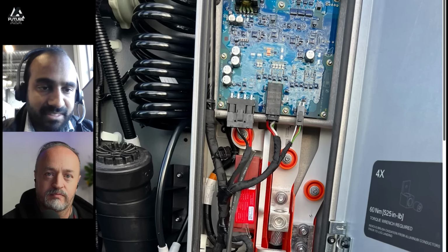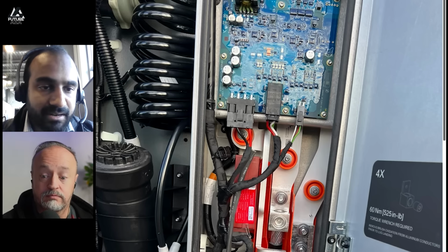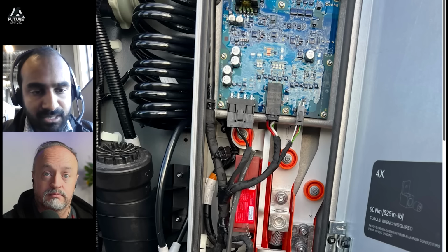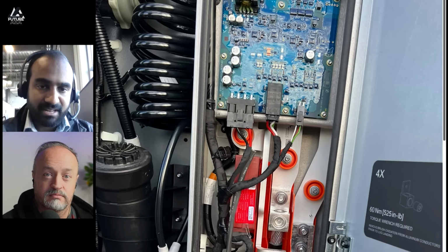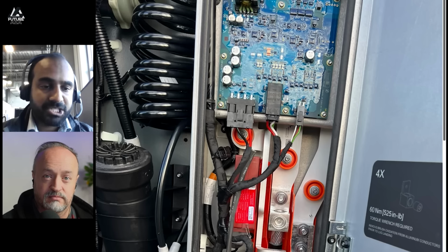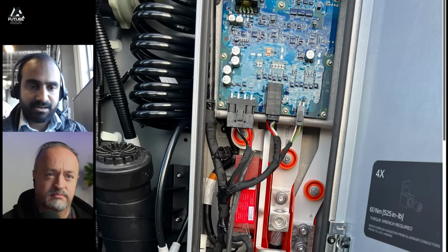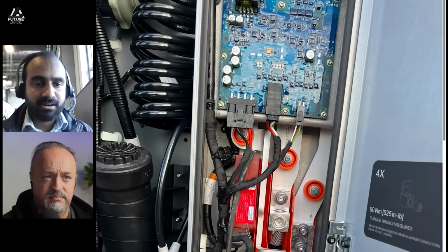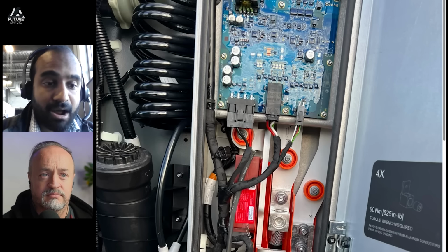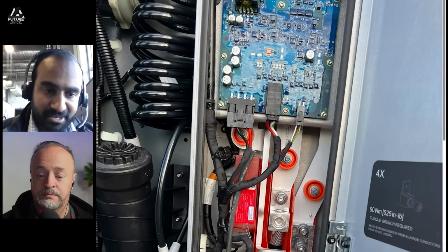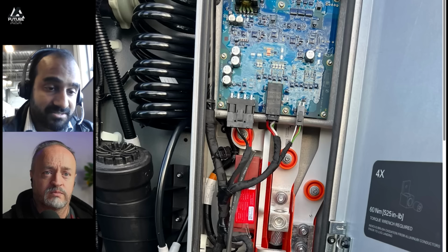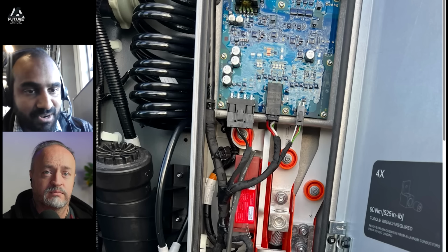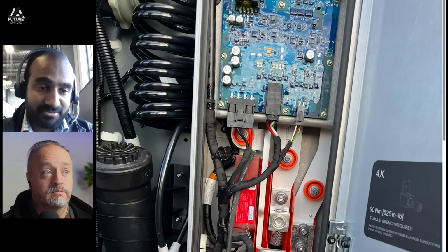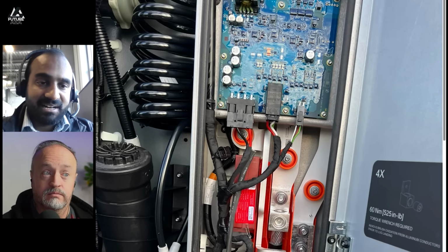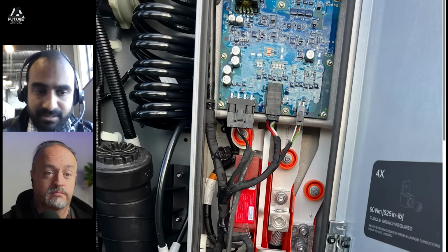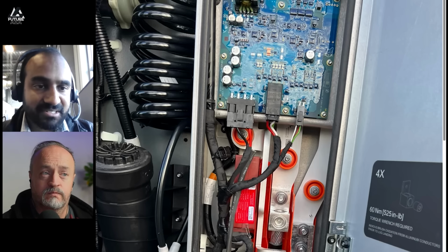There's many different things that could cause insulation to break down - a rodent eating away at a cable, just the general wear and tear of something. So one of the most important things a dispenser does when it starts to make that connection is it runs this insulation monitoring device, and that device is constantly monitoring if the current carrying cables are insulated from other aspects of the system, like ground, like the earth, in order to continue supplying current. One of the causes of charging session failure is actually that insulation monitoring device tripping, and it can trip for a number of reasons, one of which is just plugging in the cable incorrectly. But that's super critical - it's a safety critical device, in every dispenser, performing this function to keep people alive.